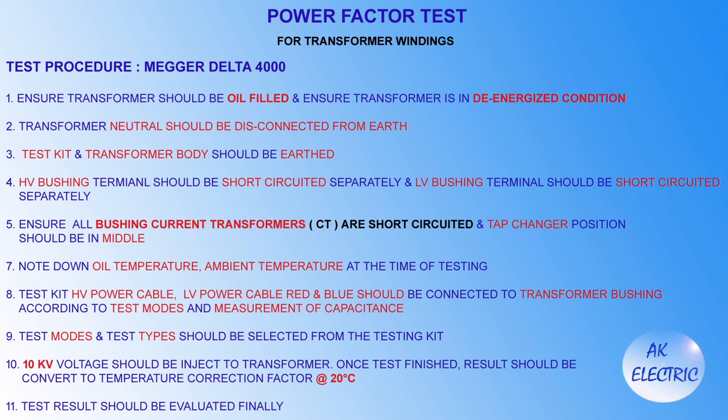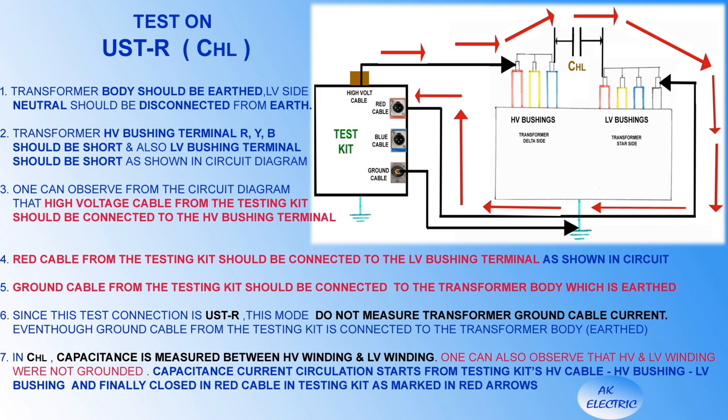The test kit, HV power cable, LV power cable, and red and blue cables should be connected to the transformer bushing according to the test mode and measurement of capacitance. Test modes and test types should be selected from the testing kit. 10 kV voltage should be injected to the transformer. Once the test is finished, the result should be corrected to a temperature correction factor at 20 degrees Celsius. Finally, the test result should be evaluated.